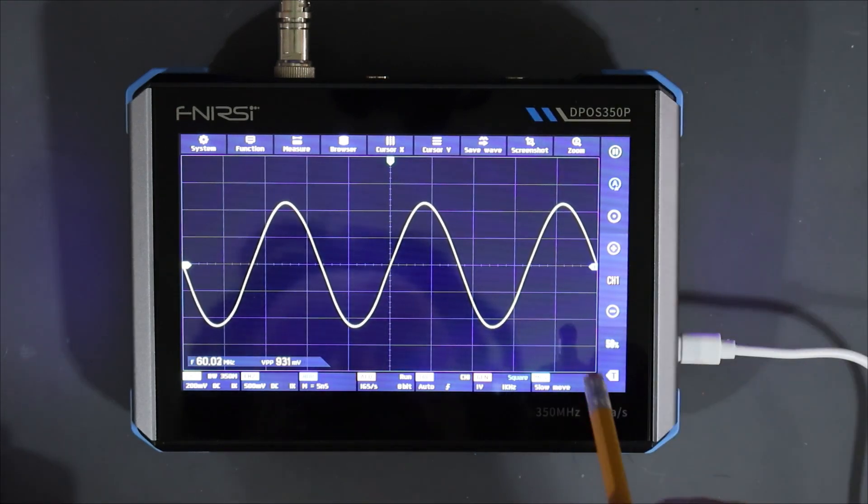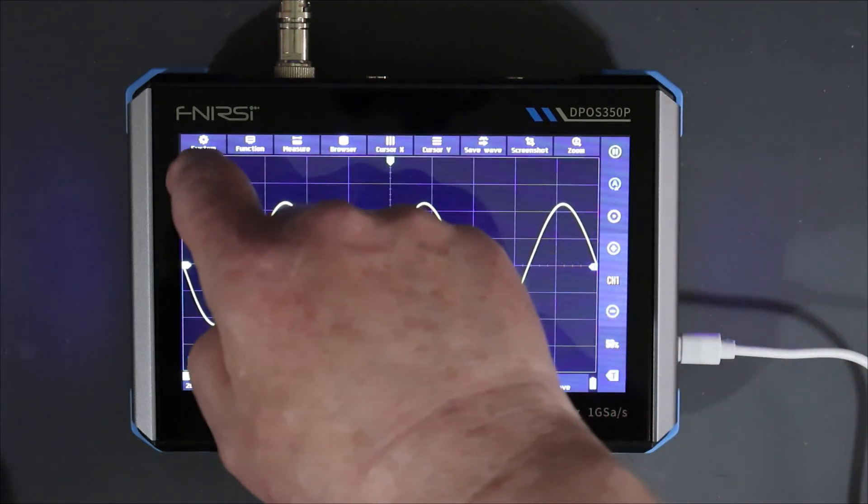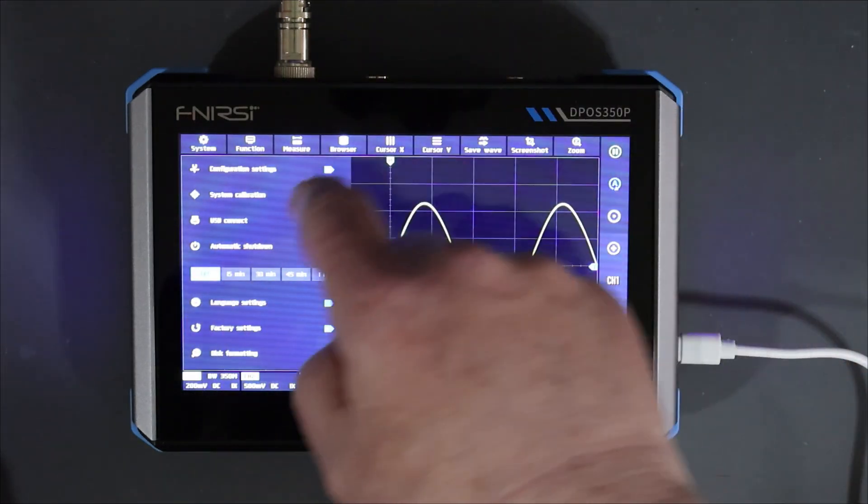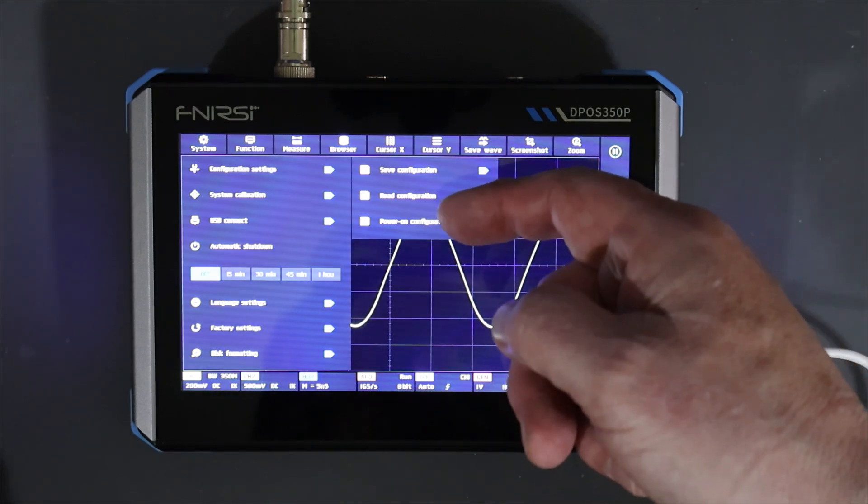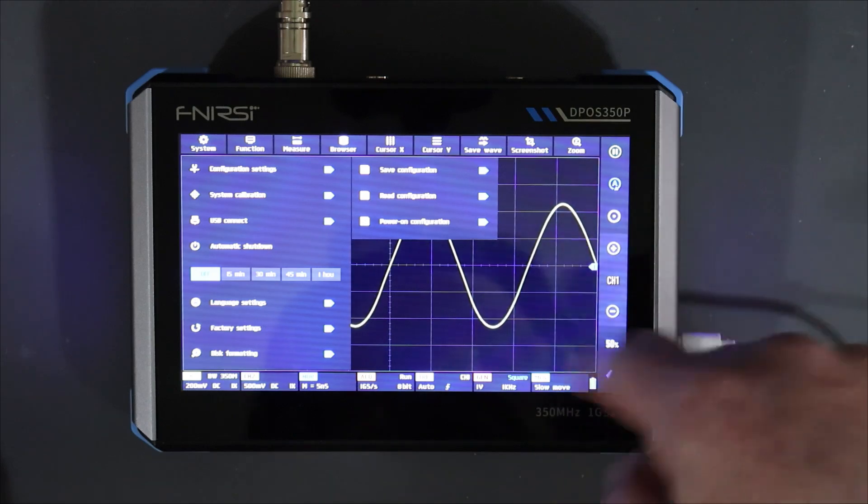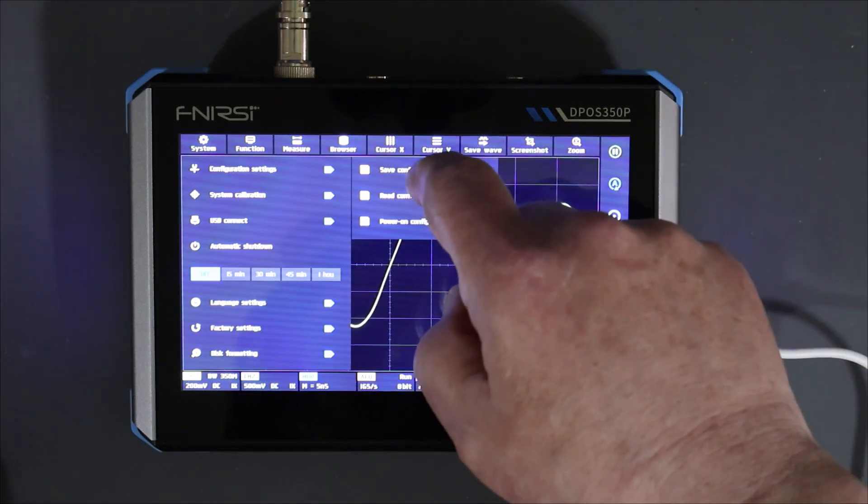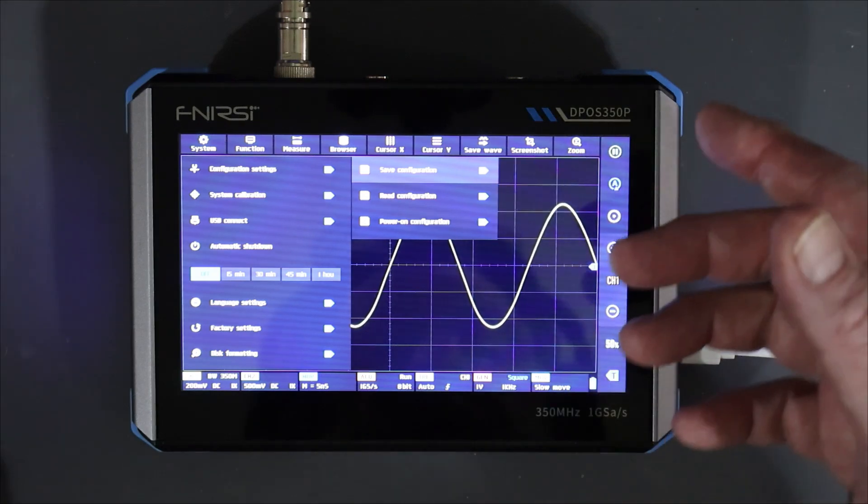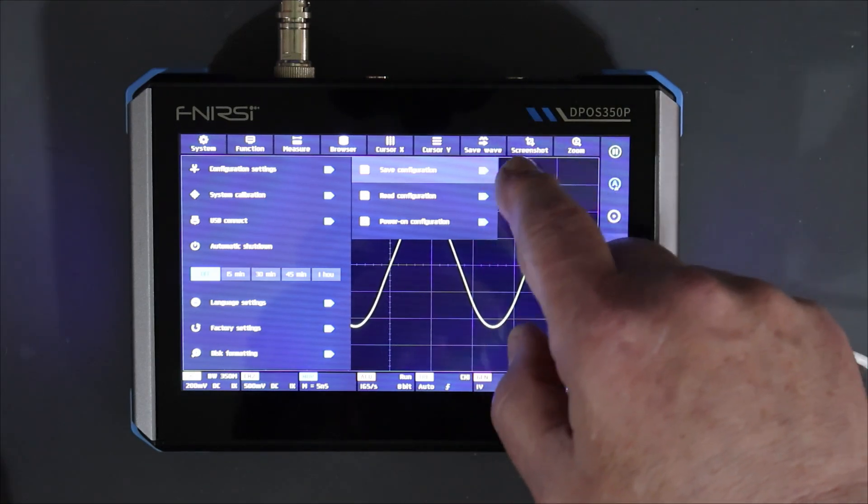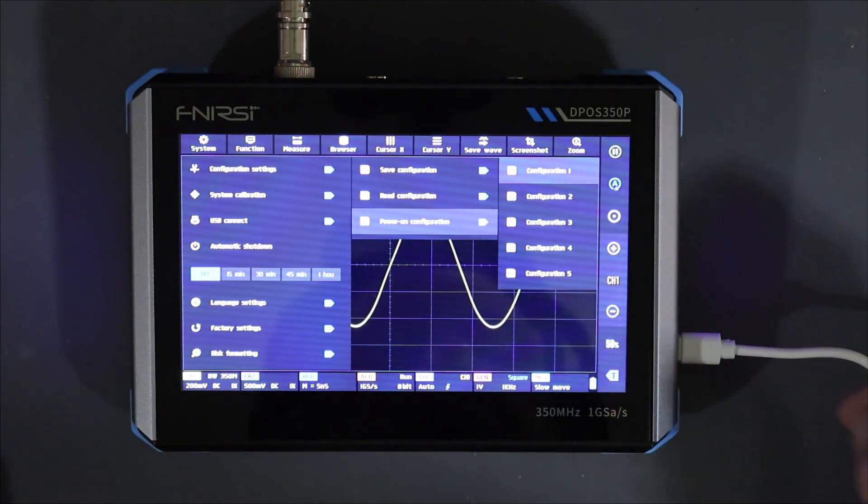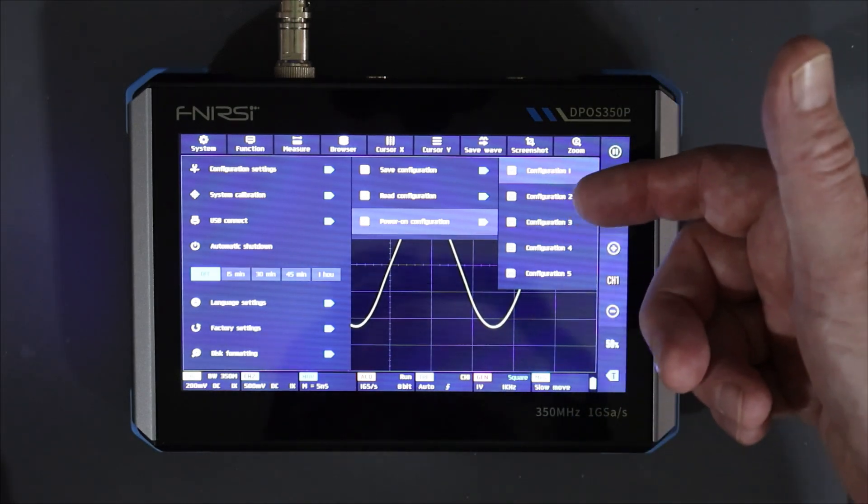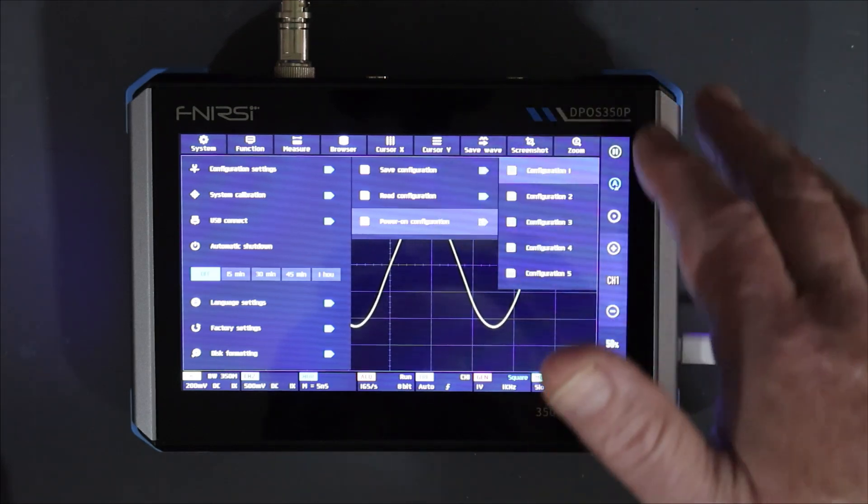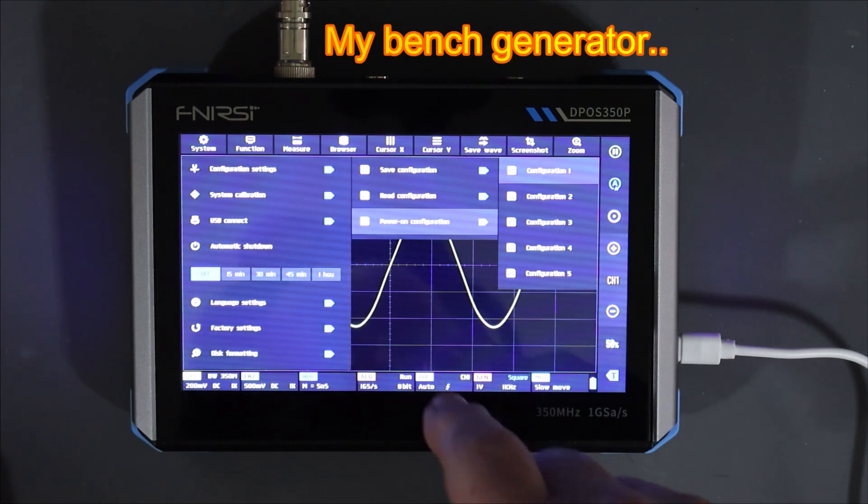Now another thing I didn't show before was saving settings. So you can save settings. In fact, it's quite good. So if we go in here to system and configuration settings. We can save configuration. We can read a configuration and we can set the power on configuration. So let's say we say we like this configuration. We're going to be using that again tomorrow. We can go in here and say put that into configuration one. So it's saved in there. And now we're going to power on configuration and it's selected as configuration number one. So every time you power it on, it's going to come up in configuration one. Or you can set configuration two, configuration three or four or five, whatever you want. That is really nice. That's a very nice feature.